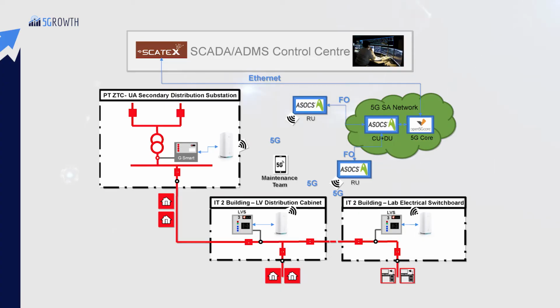In the second use case, the low-voltage sensors installed in the IT building distribution cabinet and in the laboratory electrical switchboard transmit real-time telemetry and last-gasp events to the concentrator inside the substation, which forwards them to the control center. The low-voltage sensors are connected to the substation through the 5G standalone network. These sensors and the concentrator are time-synchronized by the IT NTP server. The low latency and the high availability of the 5G network are key points to keep the low-voltage sensors timely synchronized and to ensure that the last gasp events triggered by the low voltage sensors are transmitted as soon as they are generated and while these sensors have remaining power.